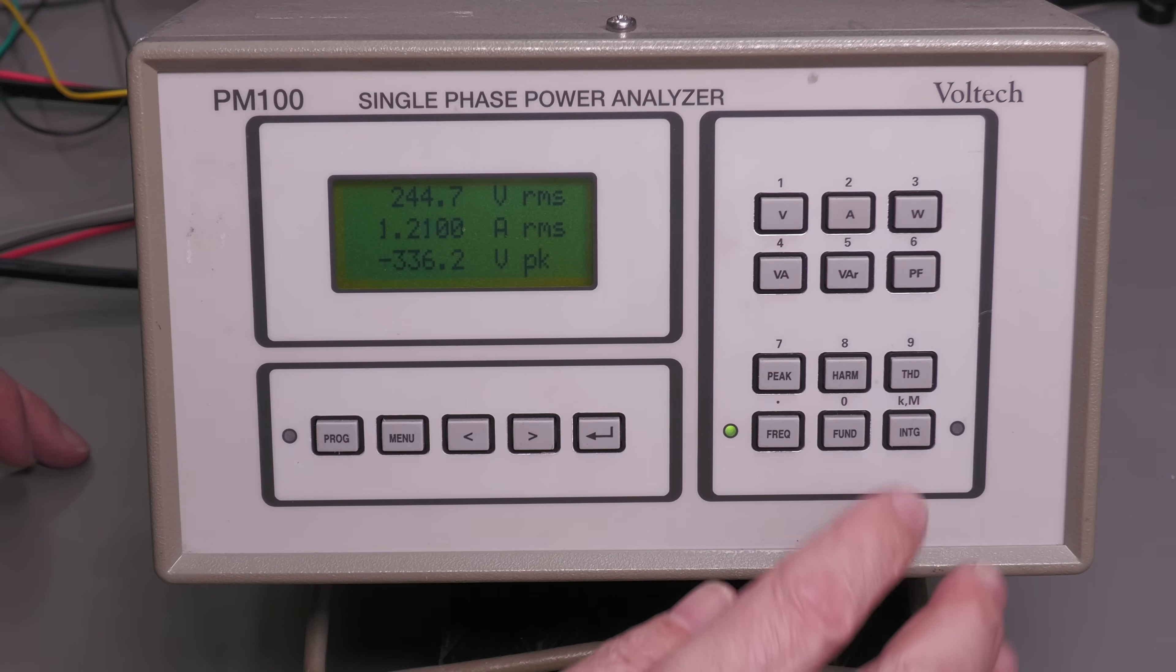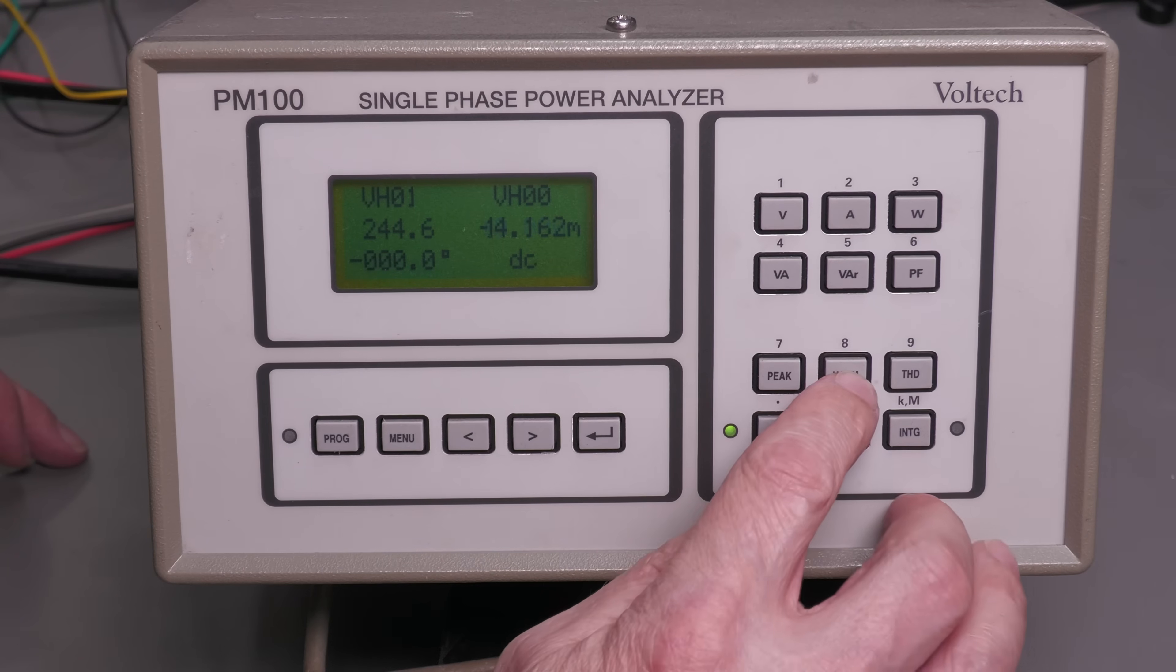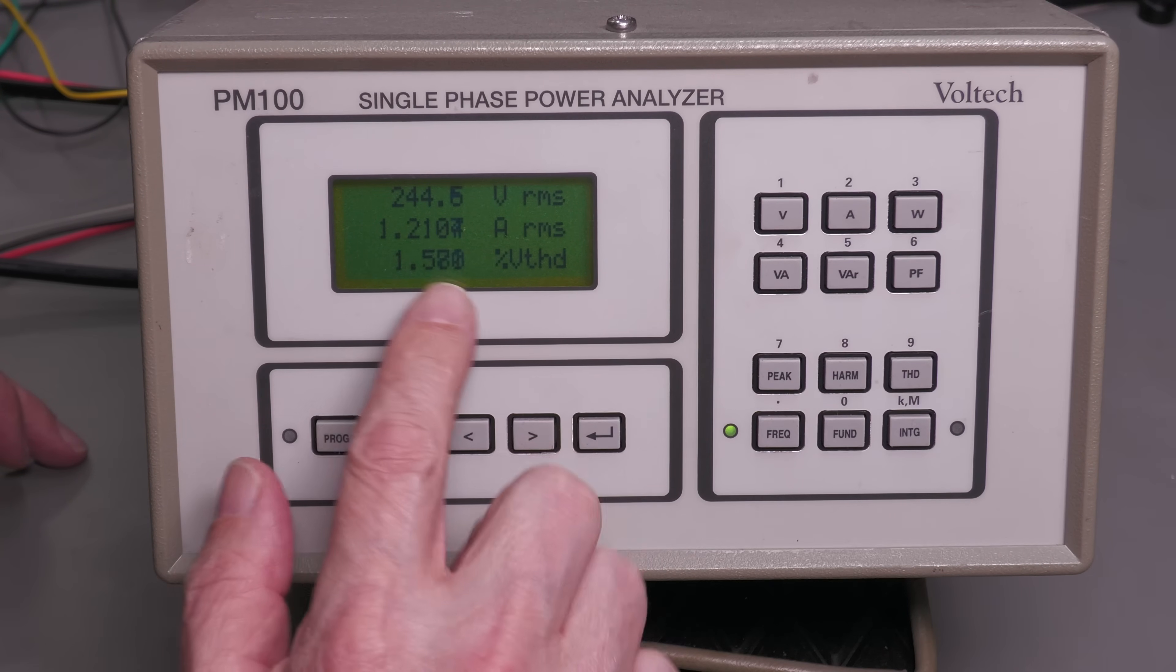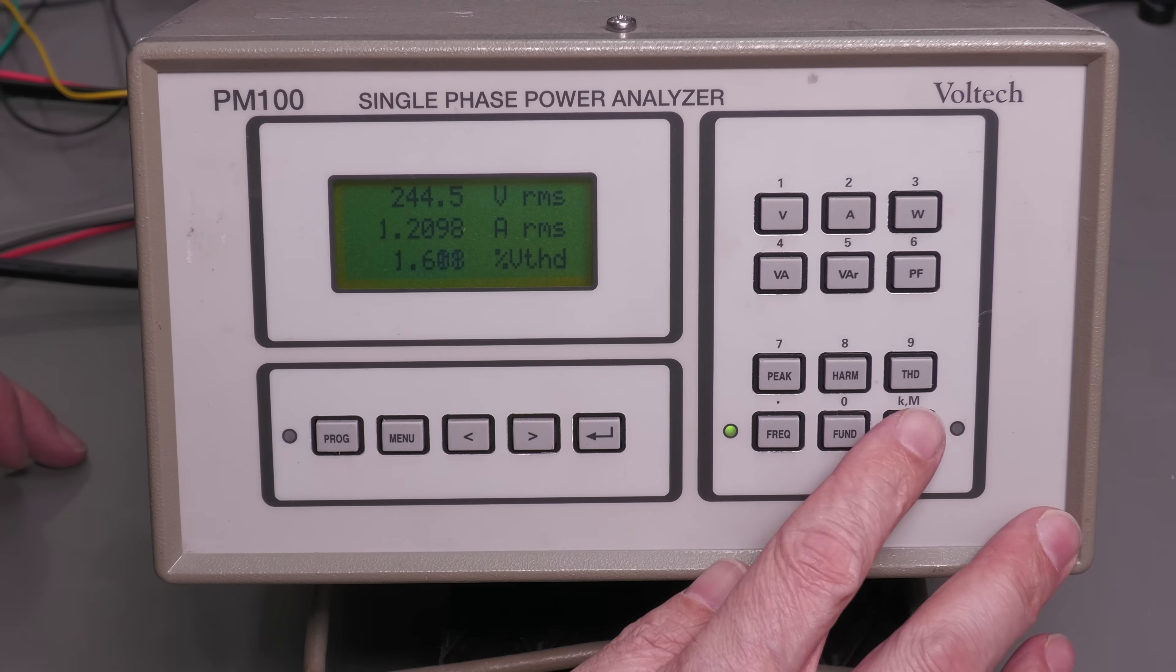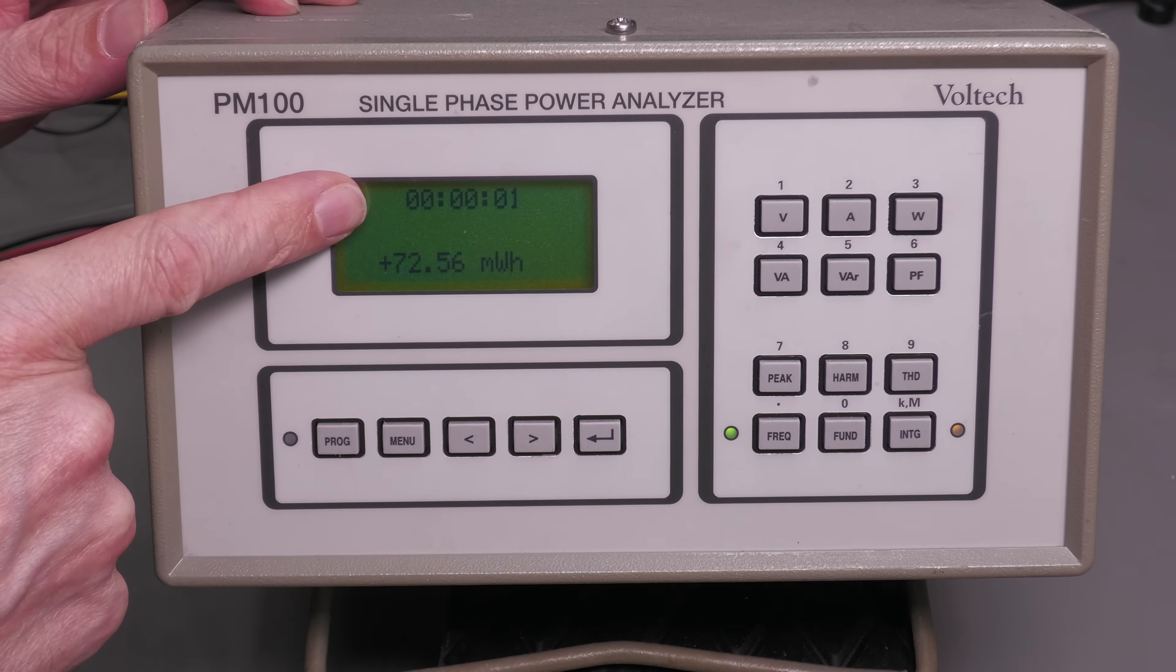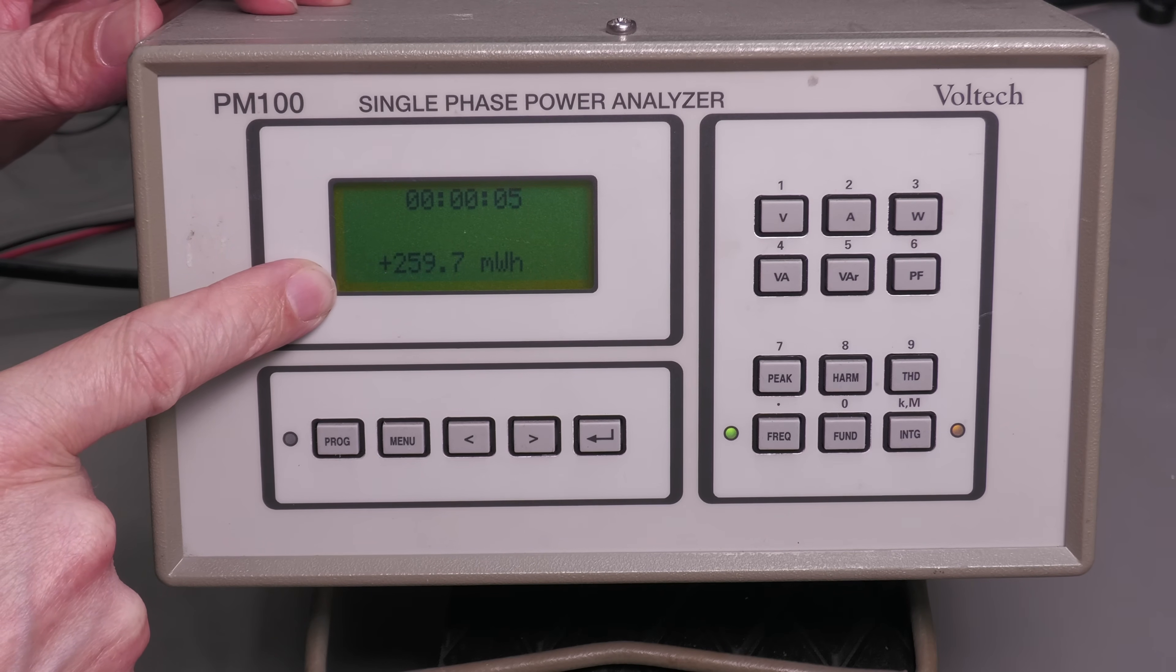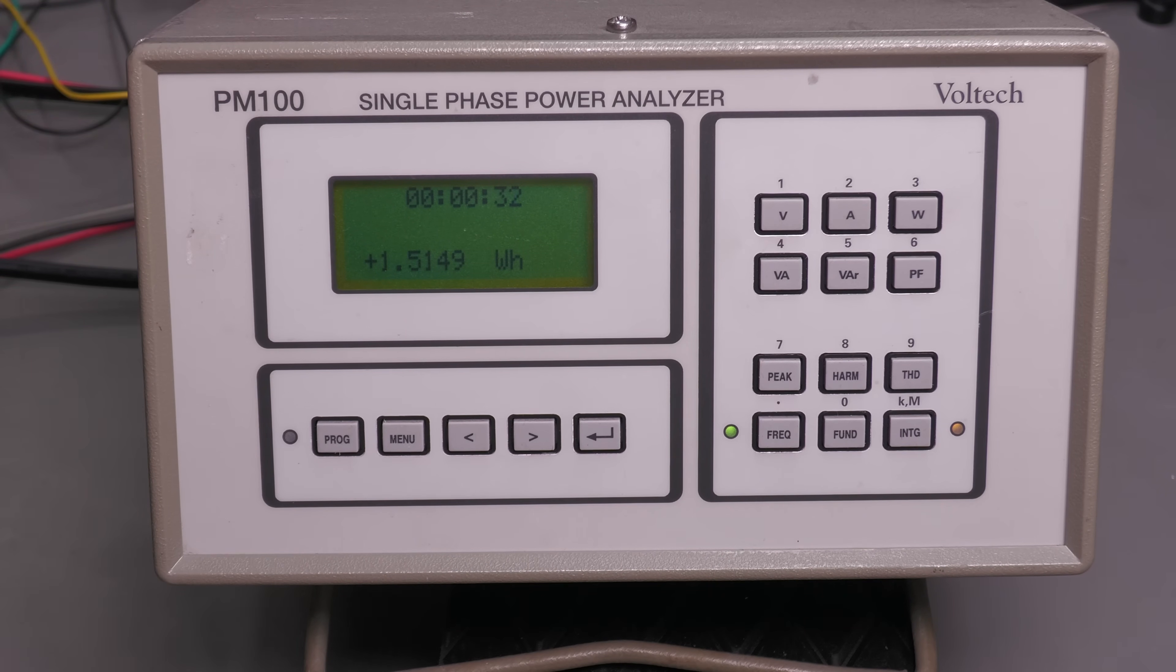Yep, that all seems to be working. We've got some data there for the harmonics. About the THD, 1.5, 1.6 percent there. That looks like it's working. And if I press the integrator button, we should get it counting up there. Yes, off it goes, and it's counting up. So it looks like it's working. This one's fine. So off onto the second unit, let's have a look at that one.